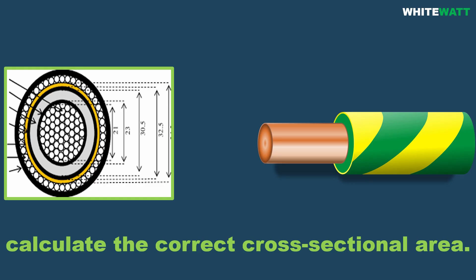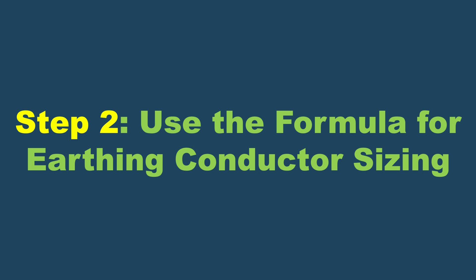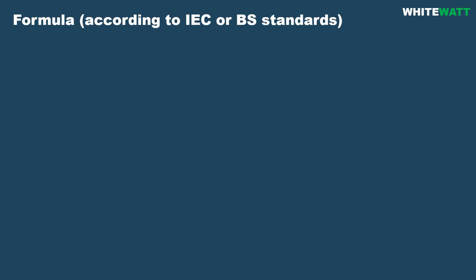Step 2: Use the formula for earthing conductor sizing. Formula according to IEC or BS standards: S = √(I² × t) / k, where S is cross-sectional area in mm², I is fault current in amperes, and t is fault clearance time in seconds.